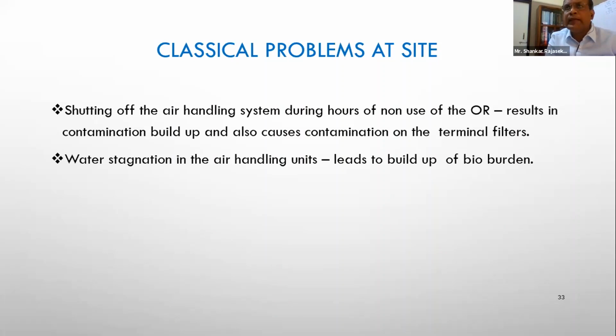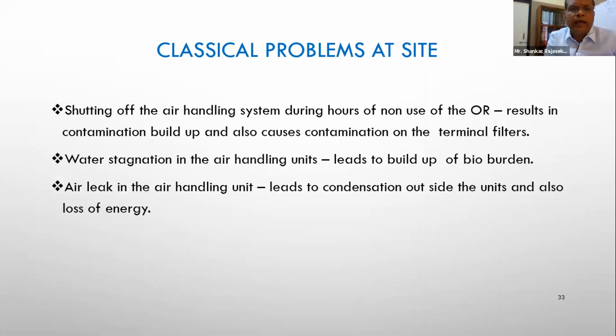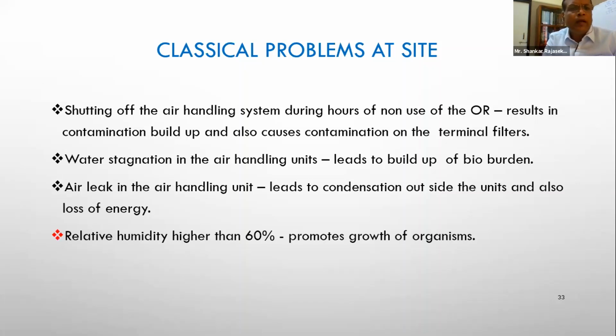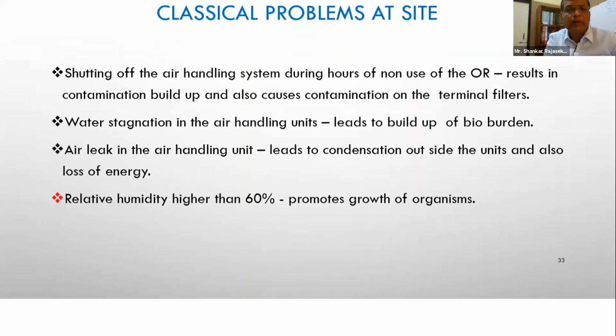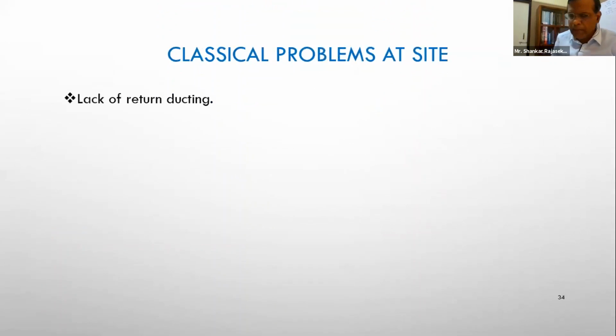Once the cases are over, if we open up the theaters and switch off the air conditioning system, all the dirt gets loaded up on the exit side of the terminal filters, as a result of which it builds up and contaminates the filters. Many times there is water stagnation in the air handling units because the drain piping and condensate piping are blocked. Air leaks in the air handling units. Relative humidity much higher than what is prescribed. Lack of return ducting. This is a big problem everywhere.